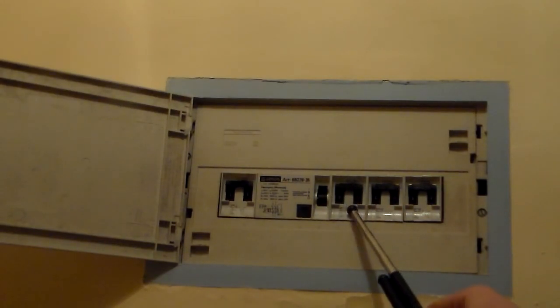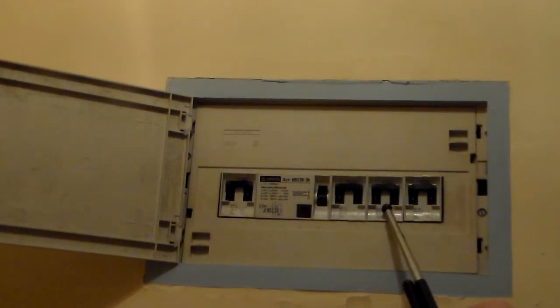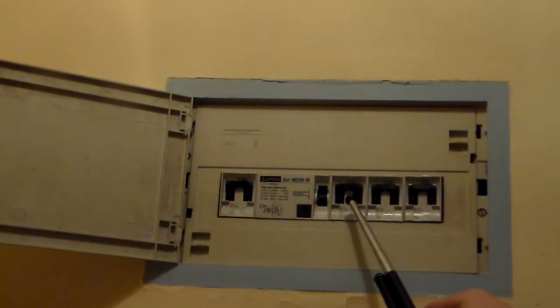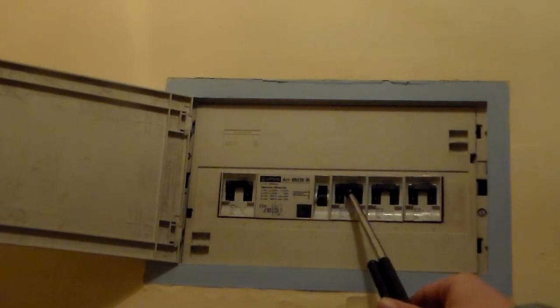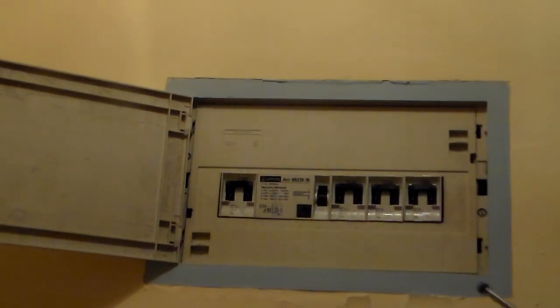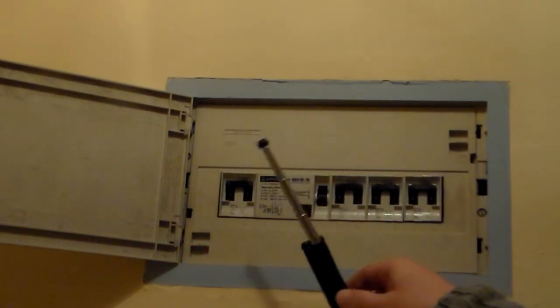Then, one by one, switch each auxiliary trip on and see which one trips the mains. This will show which line has the problem.